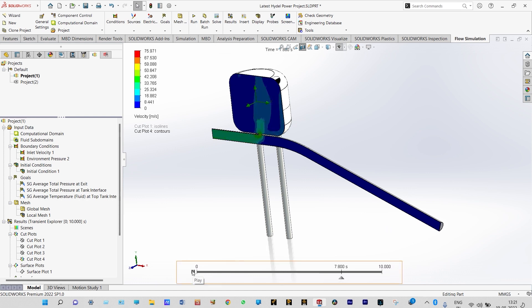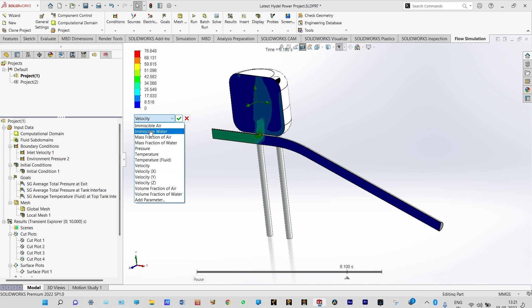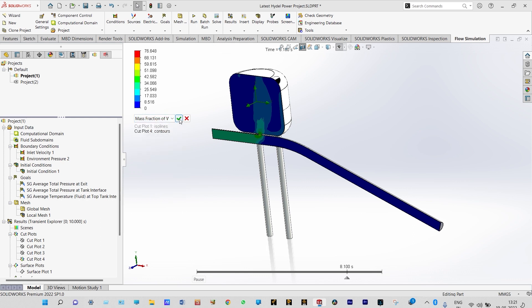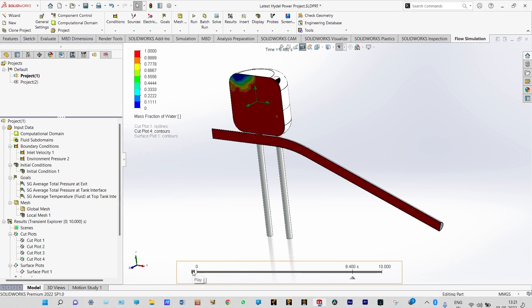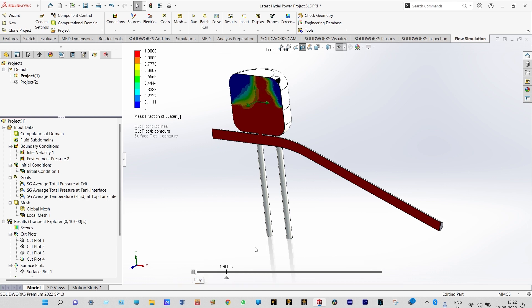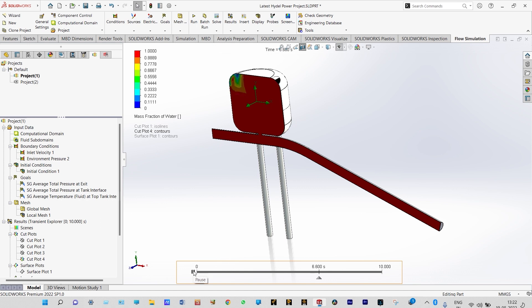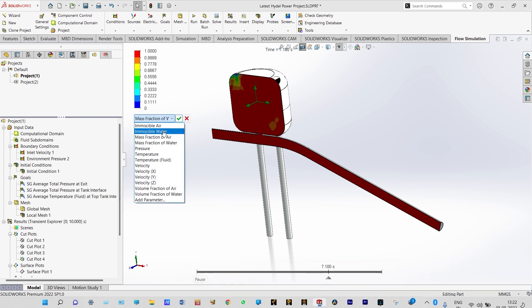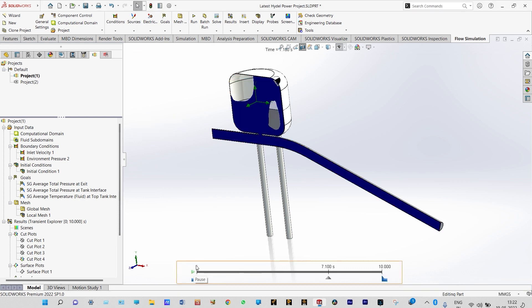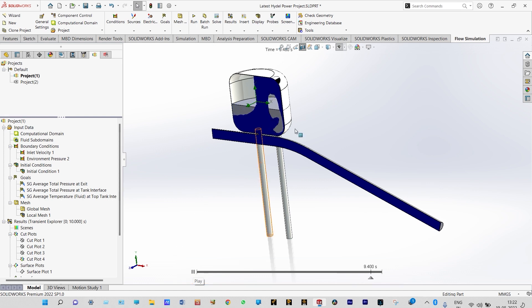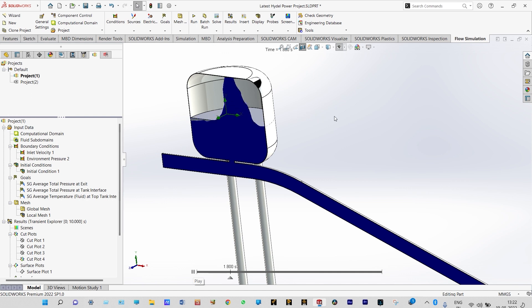Let us close it and look at something else — instead of velocity we can see immiscible water and also the mass fraction of water. Let us see the mass fraction of water first. Inside the tank we can see how water is varying, and we can see some pulsation of pressure inside this tank. Through the pipe, pressure is almost constant, which is desired — to reduce pressure pulsation inside the pipe, this surge tank has been applied. The mass fraction of water inside the tank is shown. We can also see immiscible water, which shows a sloshing effect inside the surge tank.